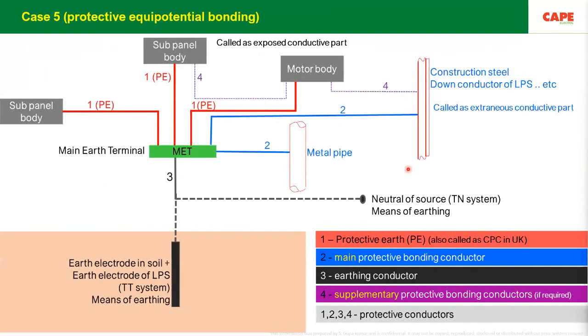Now, the case number 5. Protective equipotential bonding. What it means is, in every building, all the metallic parts except current carrying conductors or except some communication wires, all metallic parts must be interconnected in such a way that there is no shock hazard. There are rules how to connect and where to connect. Primary protection, supplementary protection, protective bonding, protective earthing, different words are there. But basically for a non-engineer to understand, very simple, every metallic part in your building must be electrically interconnected except the phase and neutral conductor to avoid shock.